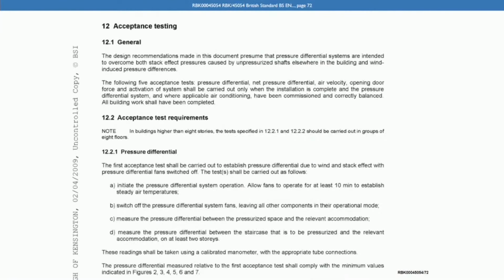So here we've got, in this British Standard, acceptance testing for pressure differential systems. And it's right, isn't it, that in section 12, these acceptance tests are different stages that must be undertaken when commissioning a smoke control system of this nature. Yeah. And if we look at section 12, each stage has instructions on how to do the test and the criteria that the system must meet. Yes? Mm-hmm. Now, let's start with the first acceptance test. That's a pressure differential test. You can see that there at 12.2.1.